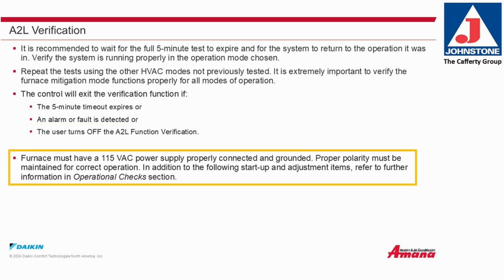The furnace must have 115 volts AC supply properly connected and grounded. Proper polarity must be maintained for correct operation. In addition to the following startup and adjustment items, you can get further information in Operational Checks section of the installation manual.